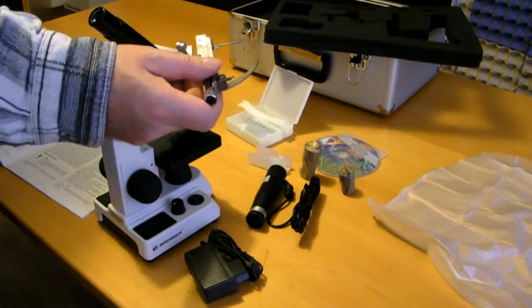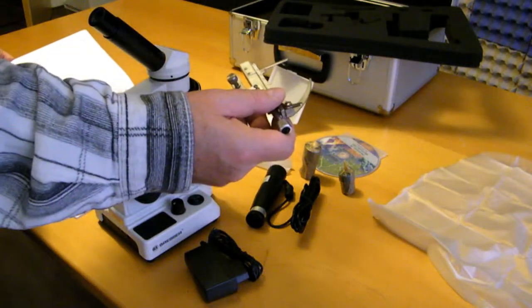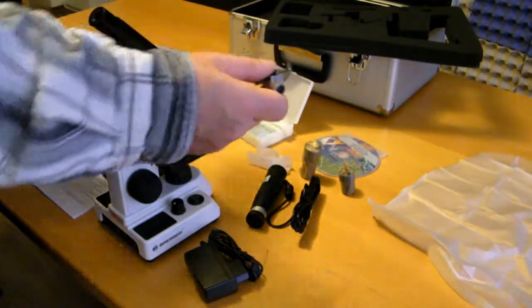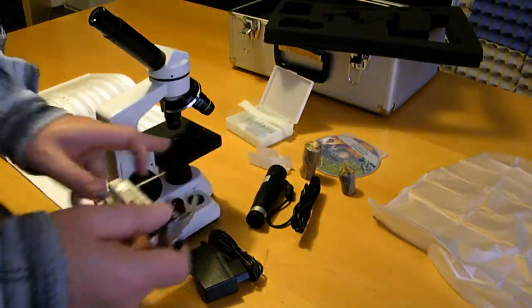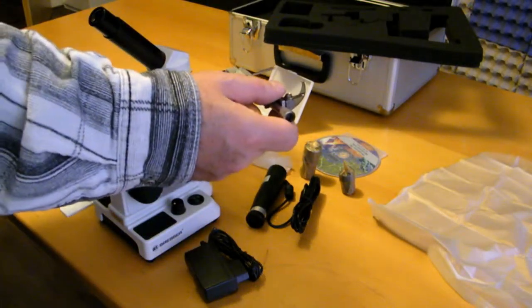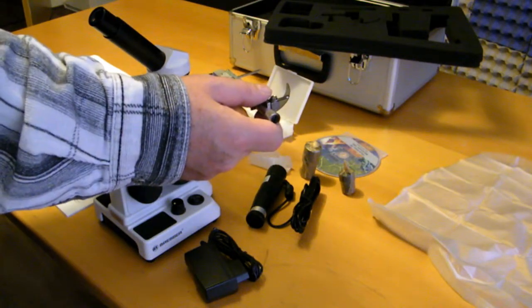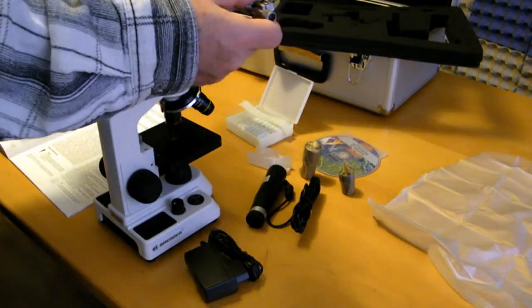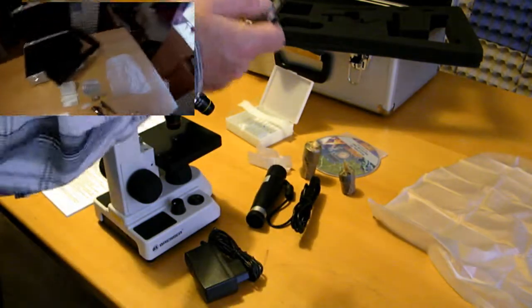So, it's simple to attach, it's written here in the manual. There are two small pegs on the bottom of the slide stage. Here and here, I think. That fits directly into the holes on the microscope stage. I see. The stage retaining screw attaches the slide stage to the microscope stage. Okay.